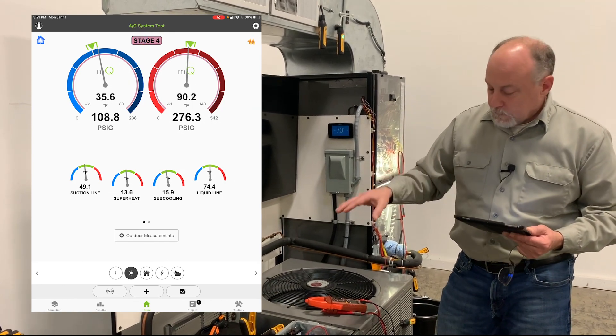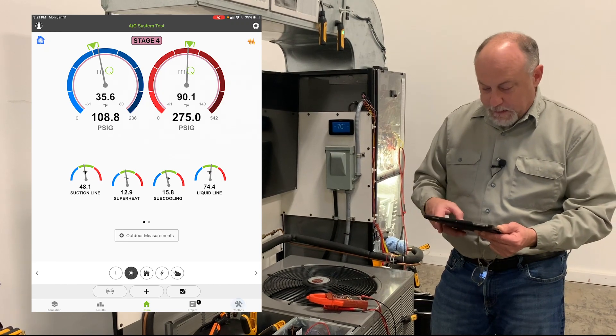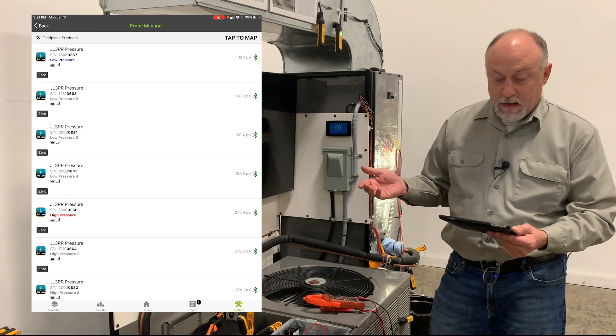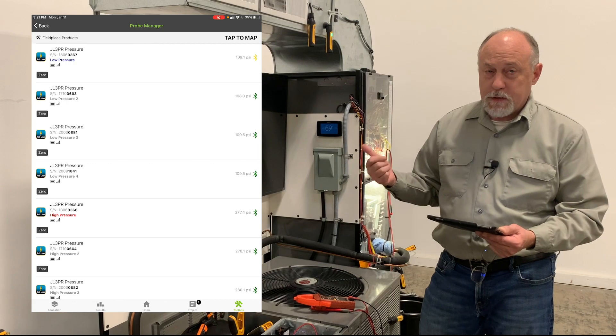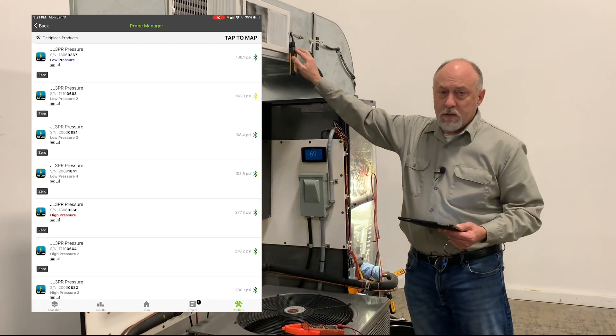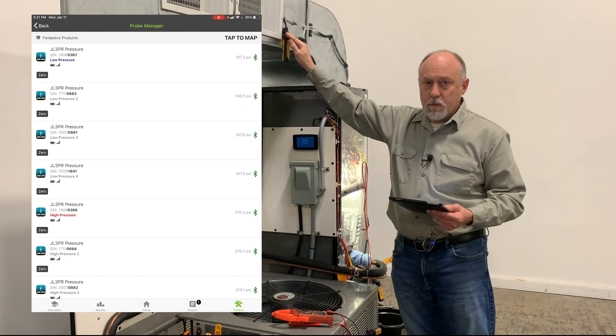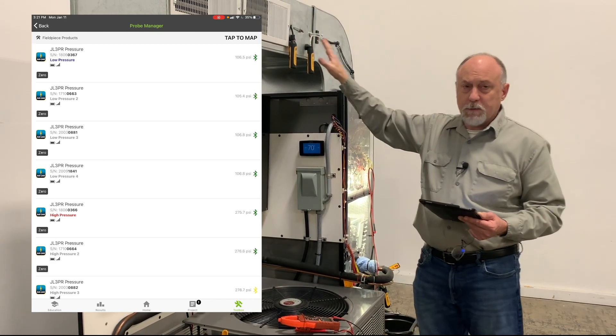What this does is it brings all the readings off of all the probes. If I go to the probe manager here, we can scroll through this. You can see we've got about 21 or 22 probes connected right now. So we've got four low pressure probes, four high pressure probes, discharge, liquid line, and then I'm doing a single supply and a single supply static — you can actually do up to four probes for the supply and four for the return, and those will be averaged out.